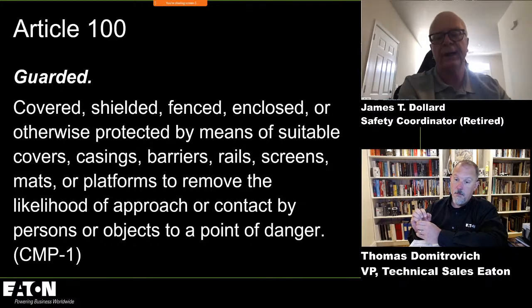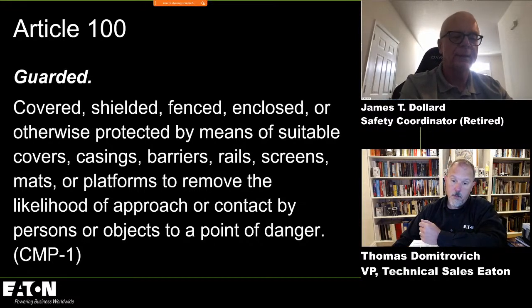But when you're verifying absence of voltage, you have to use a test instrument that makes contact. That's a requirement in NFPA 70E. Now, when you get into that in 120.5, we're going to tell you that when you go over 1,000 volts, you can use a non-contact device. And there's an exception that permits permanently mounted absence of voltage detectors, and they're listed for that purpose. And we're beginning to see a lot of those spec'd out in industrial type facilities.